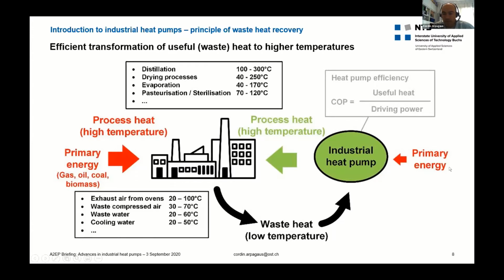It could be used as useful heat in an industrial heat pump as a heat source. Then, running with primary energy which is electricity, some process heat can be produced. So we are closing this cycle with waste heat recovery, and the heat pump is the major transformer of energy, converting the heat, waste heat, to higher temperatures. The efficiency is calculated as a coefficient of performance, which is the useful heat divided by the electrical driving power.